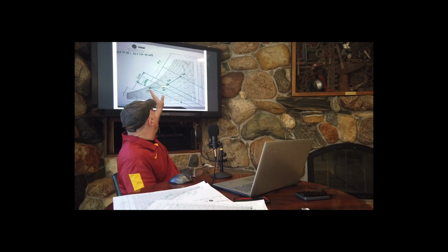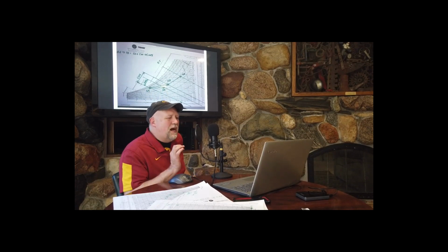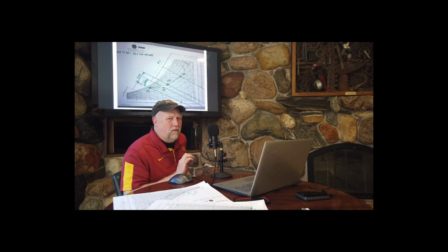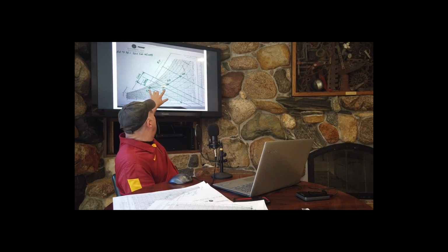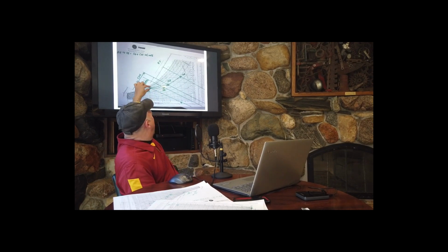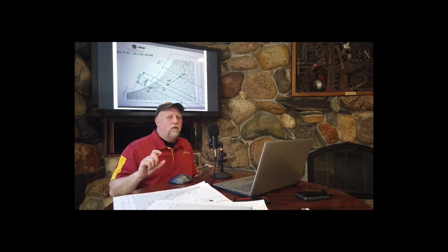Some key points on here. Notice the difference between supply air and return air. That is our space load. Notice it's mostly sensible, and if you look here, the difference in moisture is very, very low, which makes sense because if we have an office space, most of the heat generated within that space is heat coming in through the glass, lights, computers, and the sensible part of people.